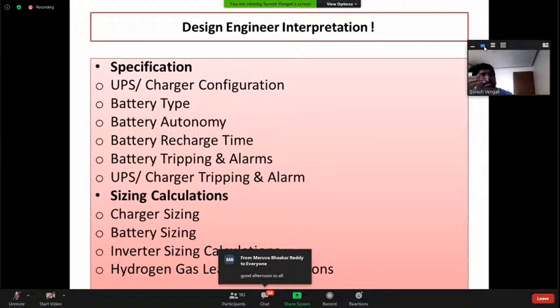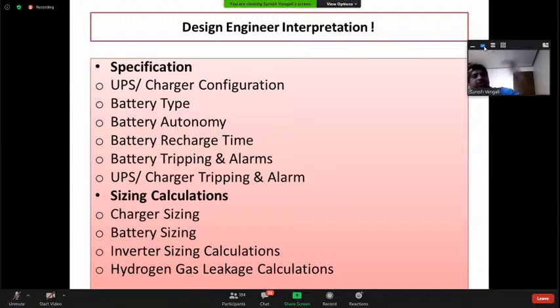So when you specify it, you need to mention these things very clearly: what is the battery tripping, at what level it is tripping. At the same time, what kind of alarms are generated in the UPS. If you are operating in any mode, it has to show on your user interface or HMI, or it has to go to your remote control systems, like PCS, ICSS, DCS, or SCADA.